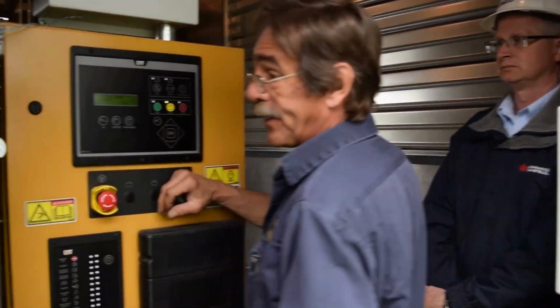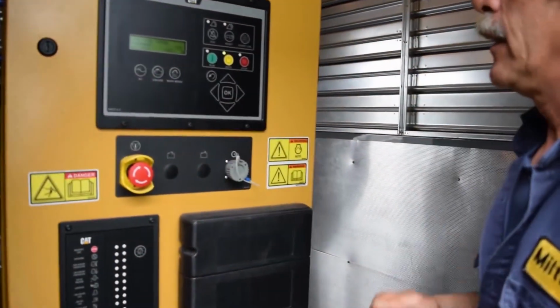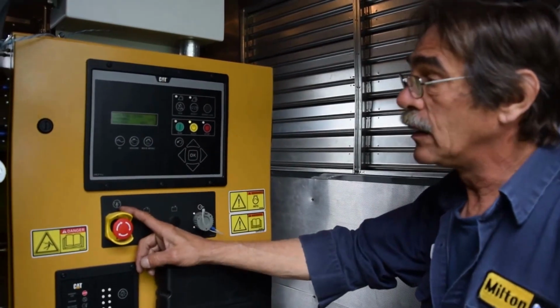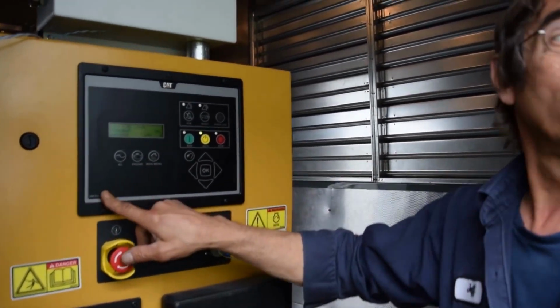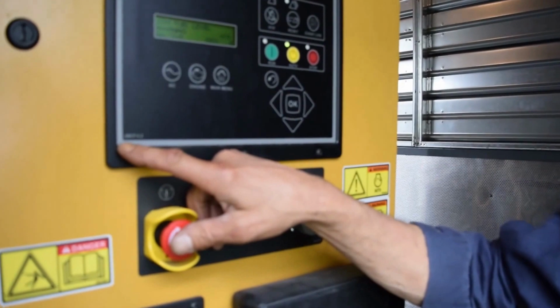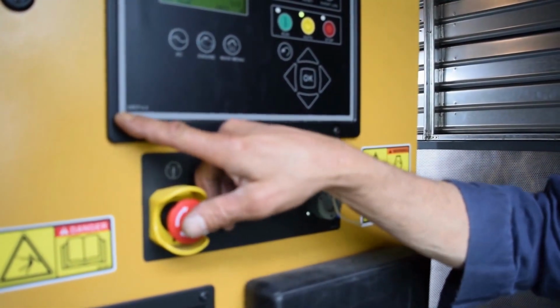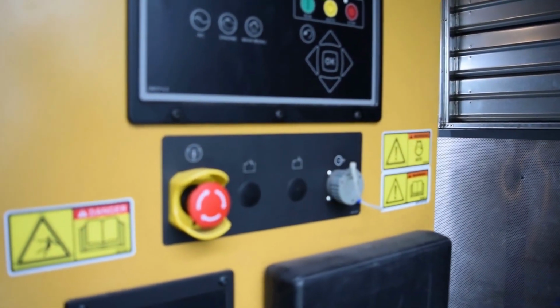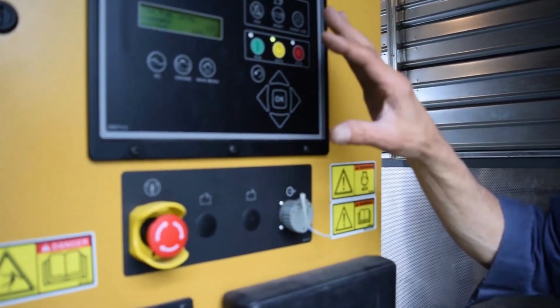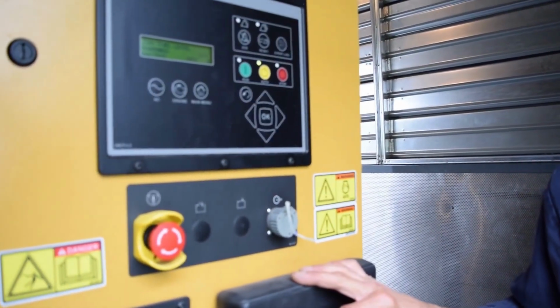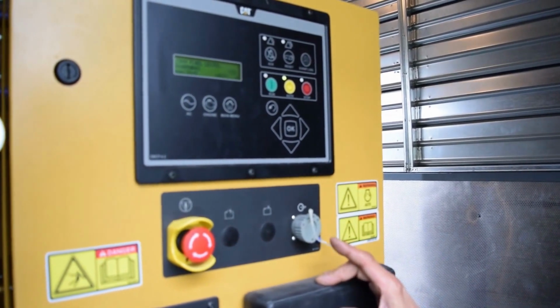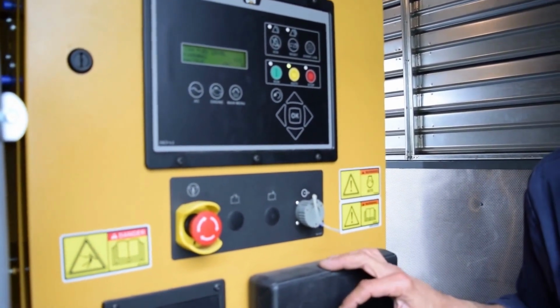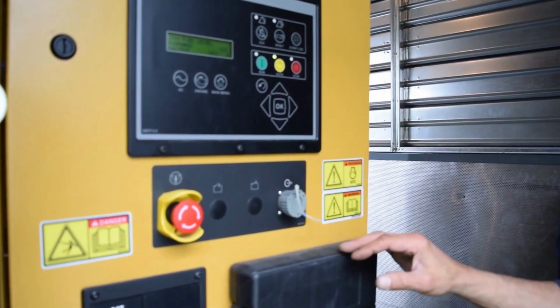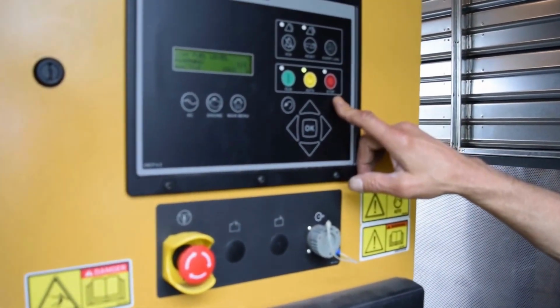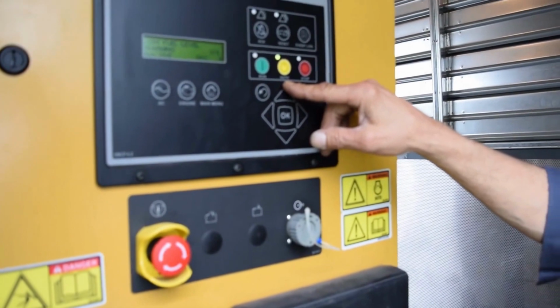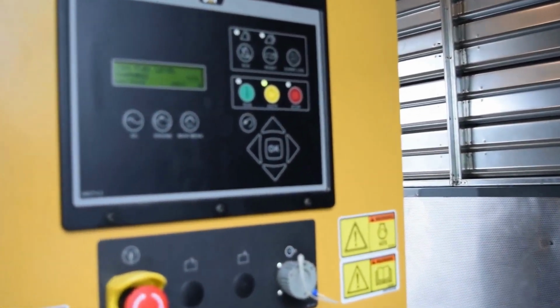And back here we have our control panel. It's an EMCP 4.2. Right down here on the bottom. If someone asks you a question, or someone's trying to help walk you through something, they need to know that, because that's telling them what you're standing in front of. There are several panels that look like this, but they don't all function the same. This is a nice panel. It's very user-friendly. It prompts you, and pretty much what you see is what it is. You have a stop button to shut it off, automatic, so it'll automatically start, and a run button to run it if you choose to run.